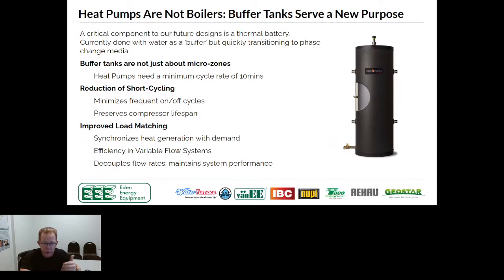It's not my opinion. That's not IBC or Enertech or Taco's opinion. That's actual research that you can read that's in white papers. Add that to your own homework. The other thing that's really nice about this is that if you get into a situation where you have mismatched loads, the buffer tank will allow you to decouple the system so you can have different flows on the unit side than you would on the secondary side going to your loads. And it also makes sure that the system is going to work properly from a comfort standpoint.